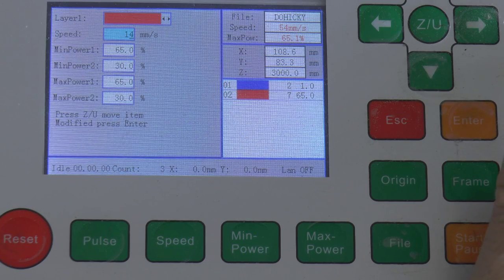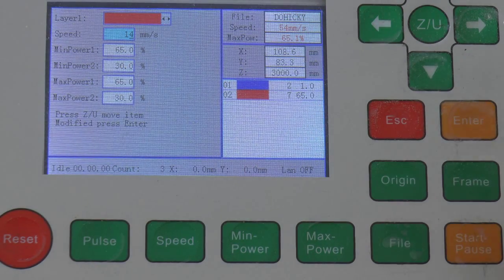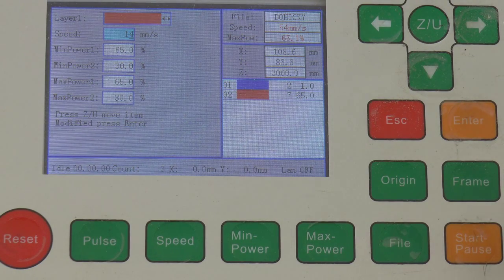If you were calibrating your machine, you would start off at somewhere like 10% and run a 10% test. Then you'd do 10, 20, 30, 40, 50, 60 - you can run up to 80 and 90%, but of course at that point you'll be overdriving your tube. Not a problem overdriving your tube for a few tests like this.